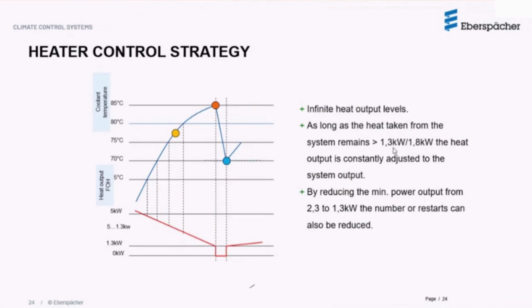It's only when it drops below this threshold that the heater is forced to switch off. By reducing the lowest output, we are reducing the number of times the heater would be forced to switch off and then restart. Whenever you switch on or restart a heater, that's the most critical time where most failures would happen. So by reducing the number of such restarts, we are eliminating the possible chances of failure.